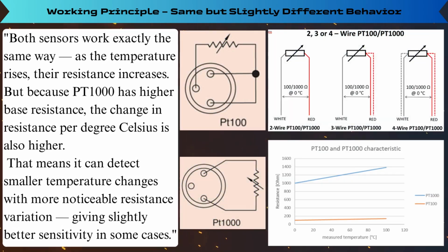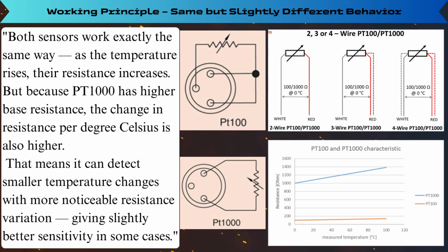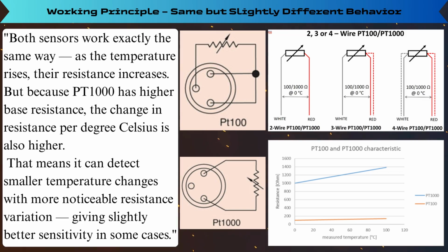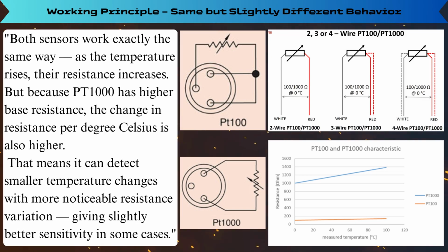Working principle, same but slightly different behavior. Both sensors work exactly the same way. As the temperature rises, their resistance increases. But because PT1000 has higher base resistance, the change in resistance per degree Celsius is also higher. That means it can detect smaller temperature changes with more noticeable resistance variation, giving slightly better sensitivity in some cases.